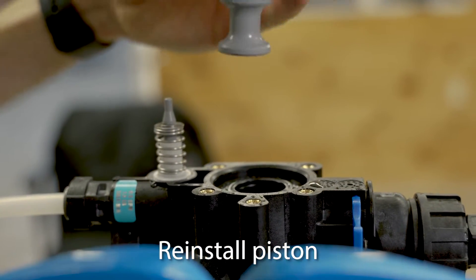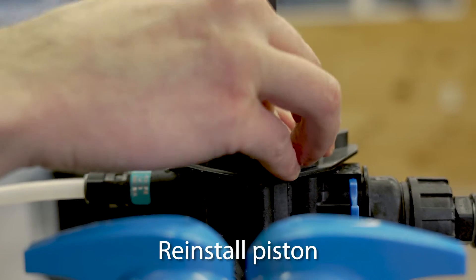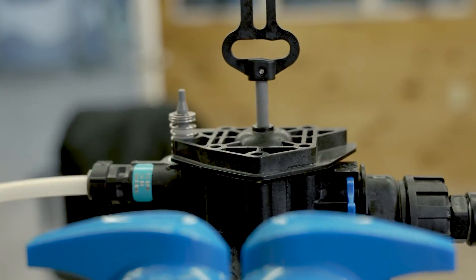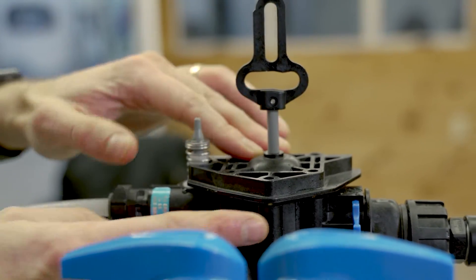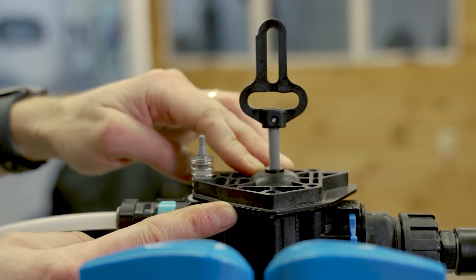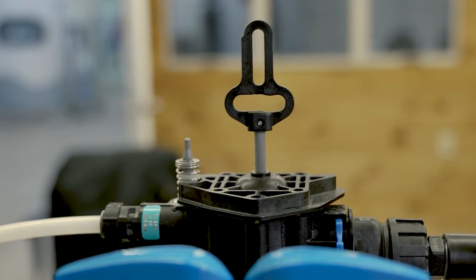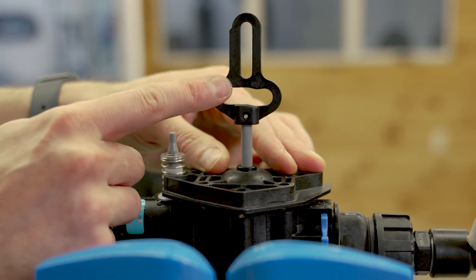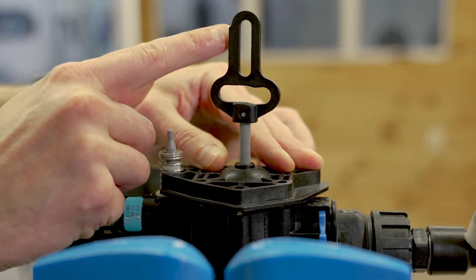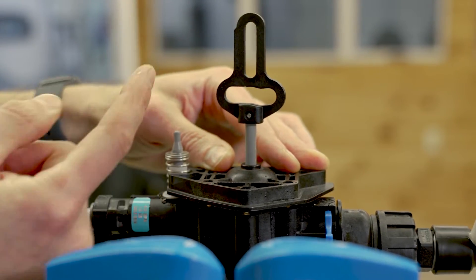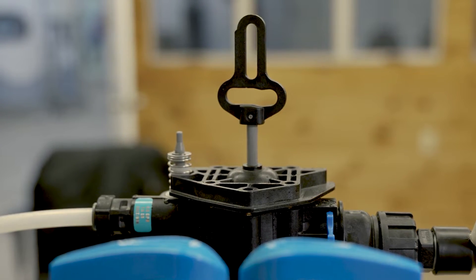We can now put the piston in and just push it down by the end plug plate. It'll sit just a little bit above the valve body; that's okay, it's going to compress when we tighten those screws down. You do want to make sure that the piston has this notch at the top facing this direction towards the inlet side of the unit.